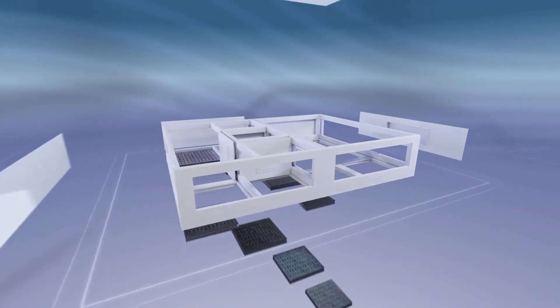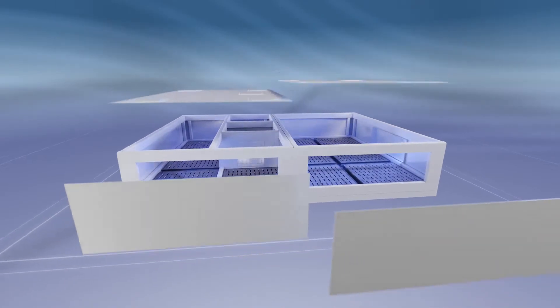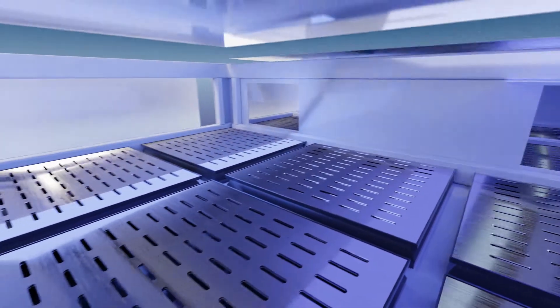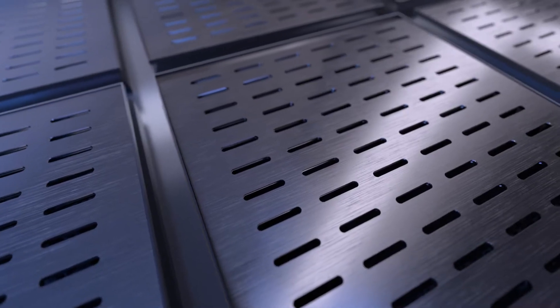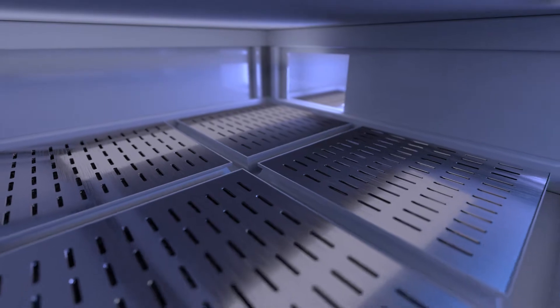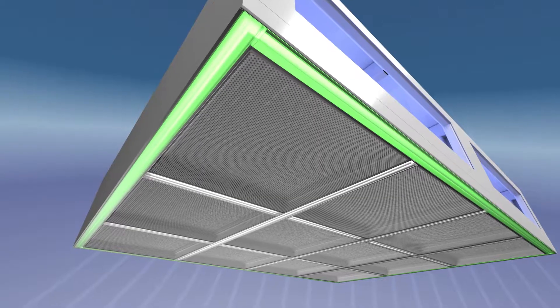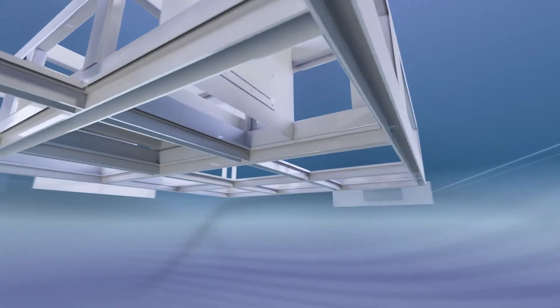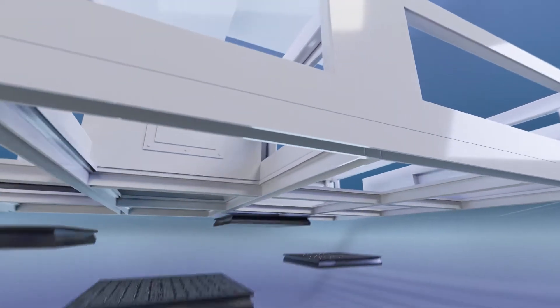The structural space frame is tightly sealed to provide a pressurized plenum, so the system is inherently balanced. Room-side equalizer dampers also save valuable balancing time — simply set it and forget it. Clean Suite's high-performance diffuser grills are engineered to pharma and cleanroom specs for gapless unidirectional flow.